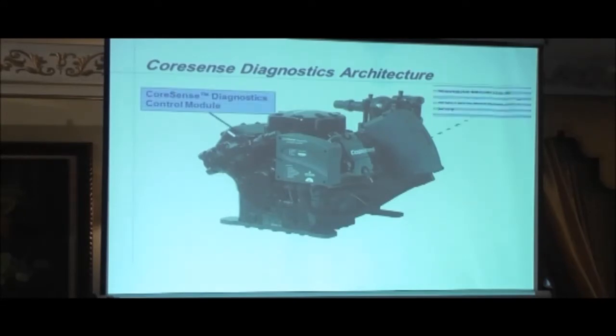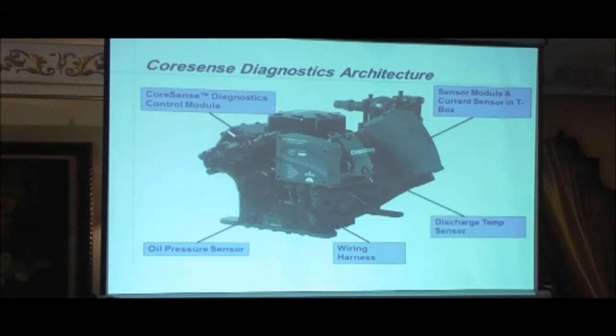So now this is the architecture. The main control module is this component here. Right? This is what we refer to as the control module. The compressor will now come fitted, standard, with an oil pressure switch. So the oil pressure switch is already included in the supply of the compressor. We have our discharge temperature protection. So you see there's a probe connected to the head, and that is connected to the control module. We have a wiring harness that will connect the control module to the current and sensor module, and this basically replaces the old INT69 that was supplied with the compressor.